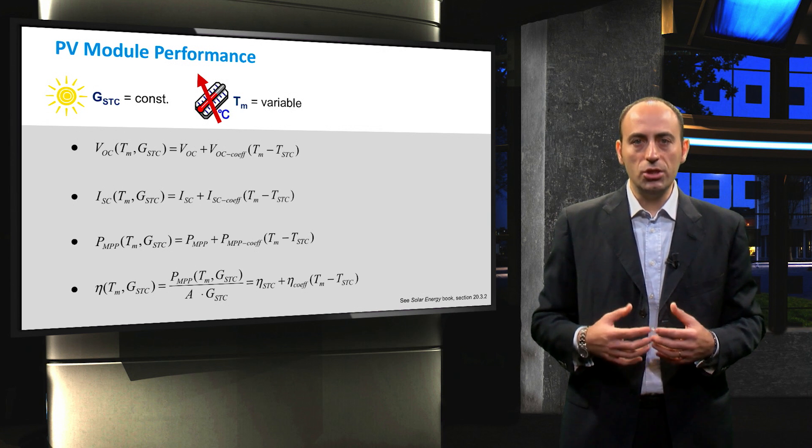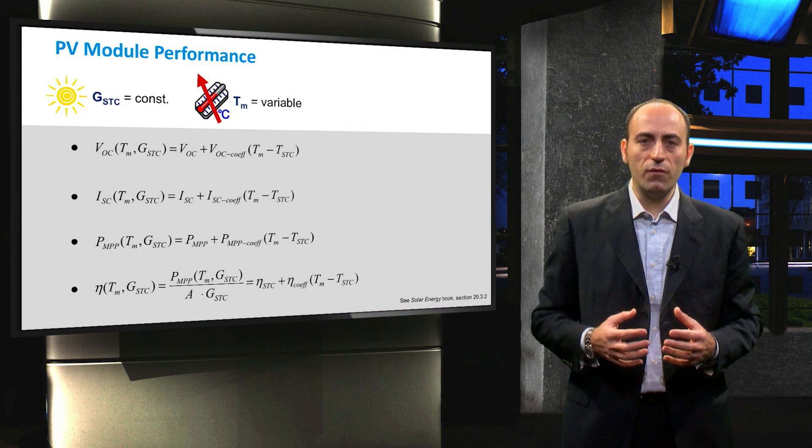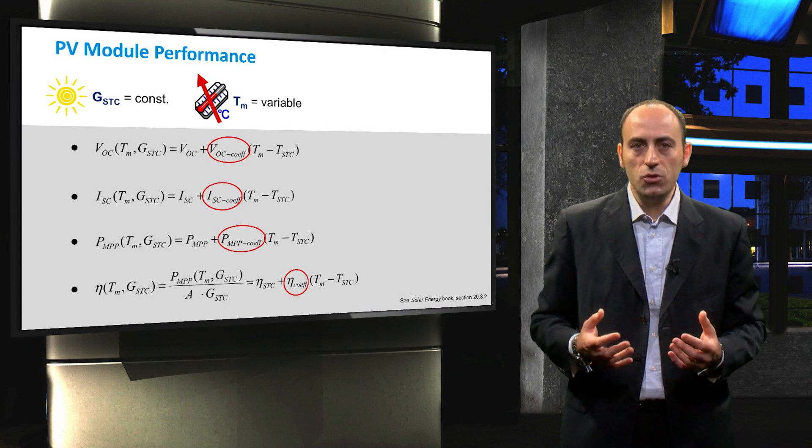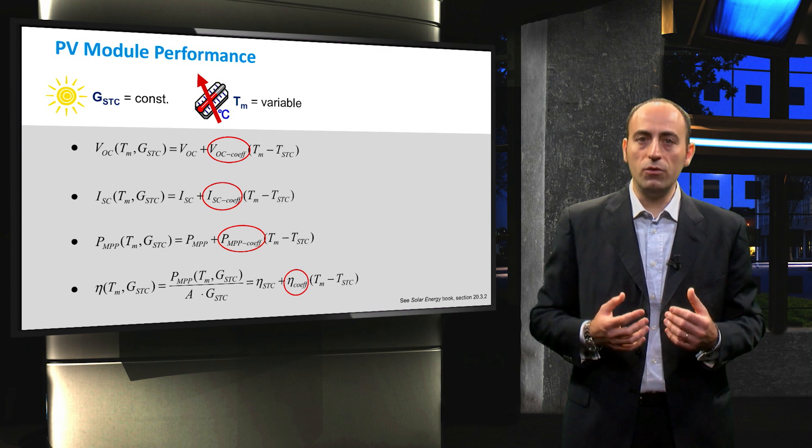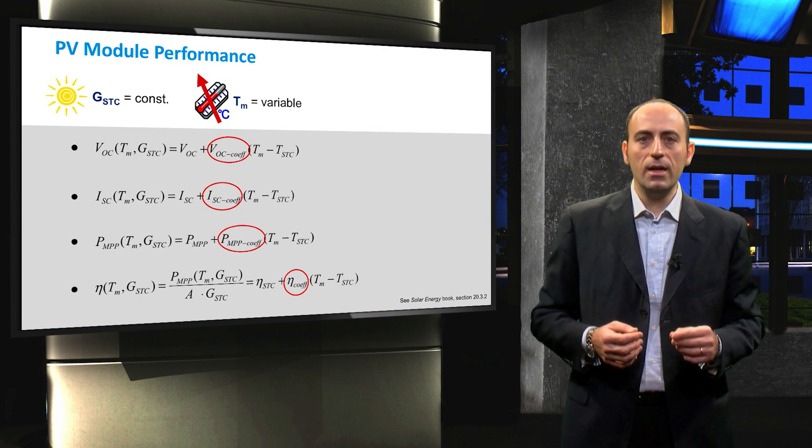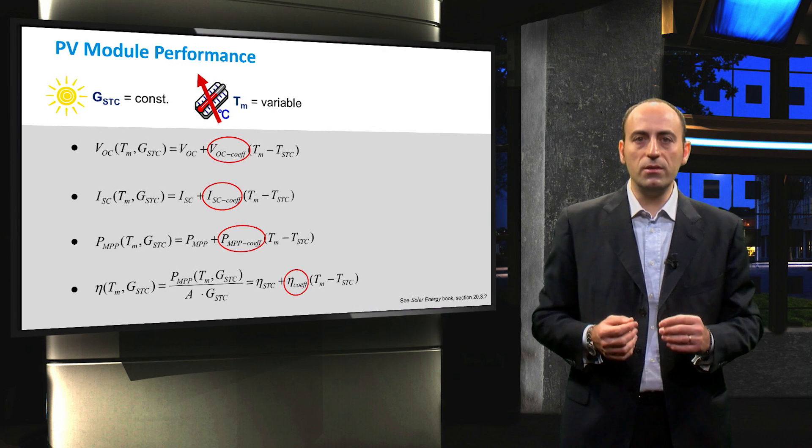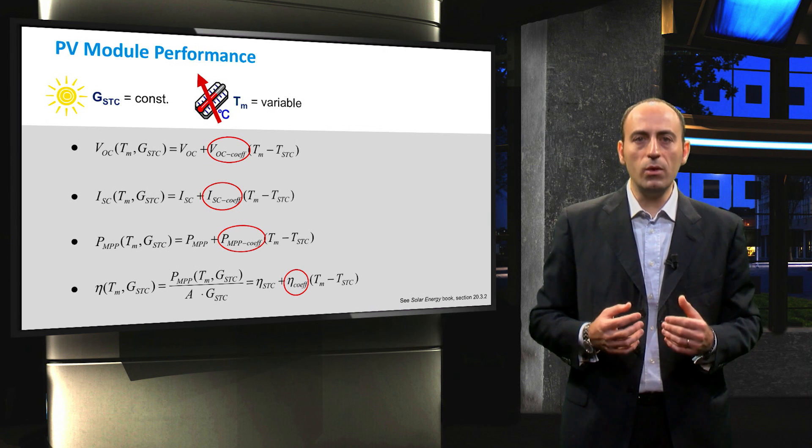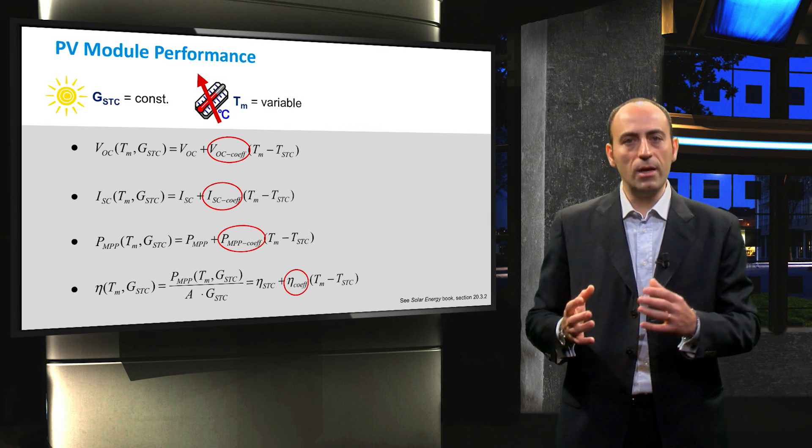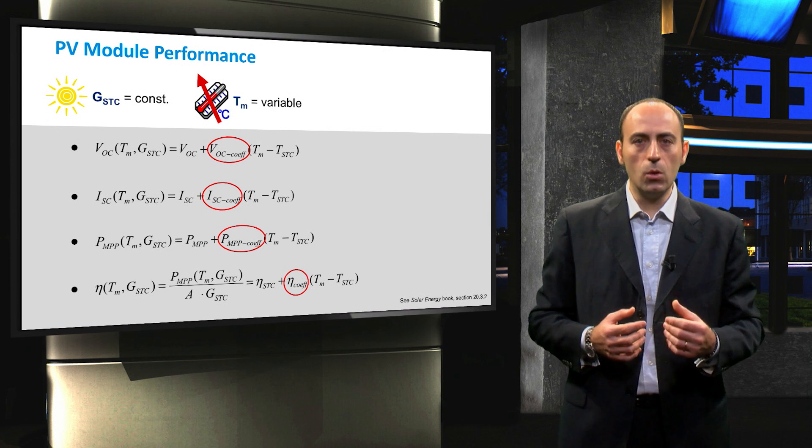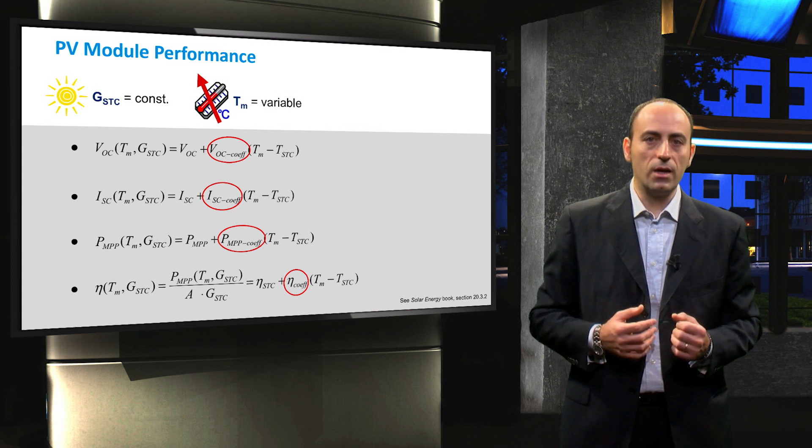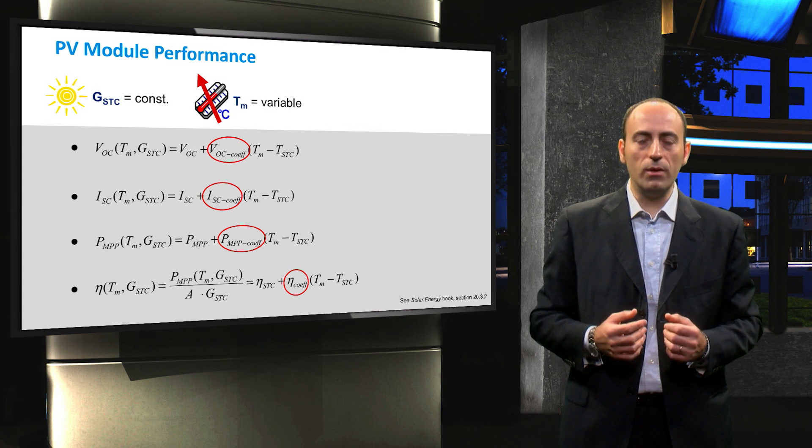Usually, in the datasheet of the PV module, the temperature coefficients are provided by the manufacturers. So, assuming that we know the temperature of the module at a certain moment, then the VOC, for example, is re-evaluated from the VOC at standard test conditions by means of a simple linear correlation where the temperature coefficient indicates the slope of the deviation. The same applies also for the short circuit current and the maximum power point and the efficiency.